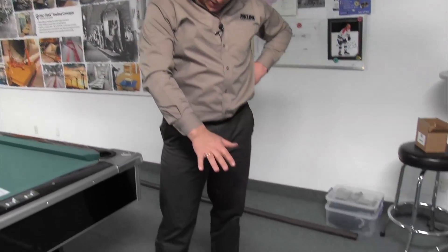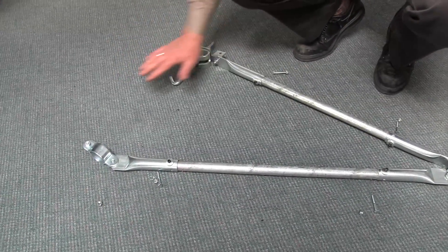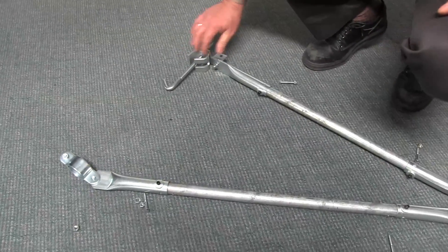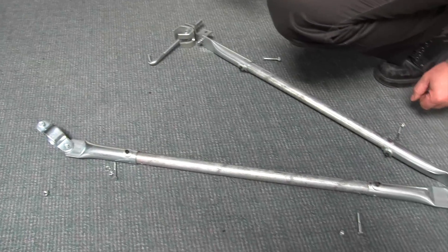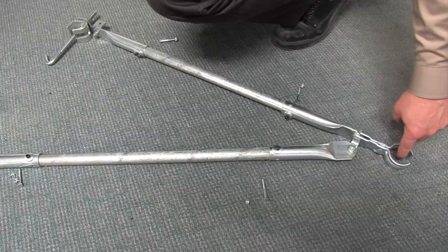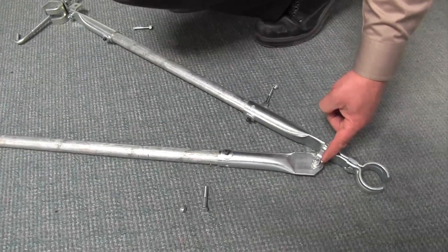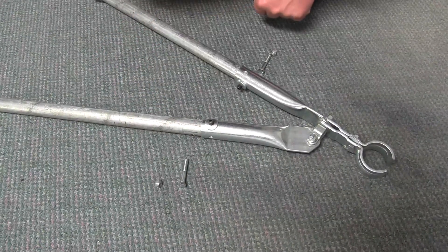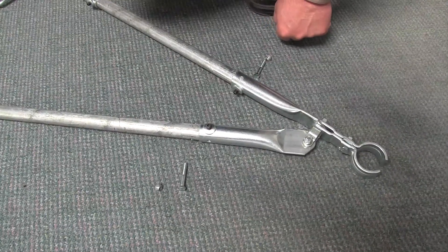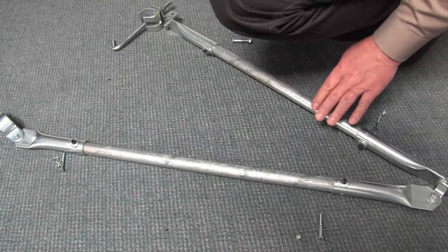Looking at the various components laid out on the floor, you'll get an idea of how this will end up. We have a TH-300 track hanger clamp, which comes with a clamp portion and a sleeve. There is also an additional sway brace attachment with its own sleeve. The pipes used to support the system are standard three-quarter inch ID water pipes — you can get them at any hardware store, they come in galvanized or black, and they are cut to length to suit.